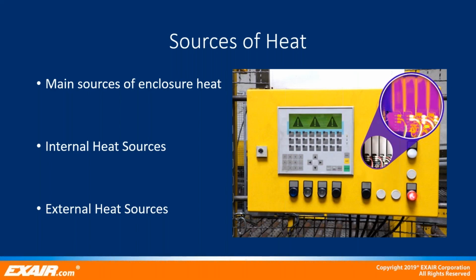These sources include engine rooms, industrial ovens, and even solar heat if the enclosure is located outdoors or in direct sunlight. At higher temperatures, the efficiency of equipment decreases. It may cause component damage or failure. For example, a modern VFD typically has an efficiency of 93 to 97% and is designed to operate below 95 degrees Fahrenheit. For every degree increase above the maximum intended operating temperature, efficiency is derated by 2%, in addition to the risk of equipment failure. It is important to properly match a cabinet cooling solution to your unique application to verify it will properly meet your needs.